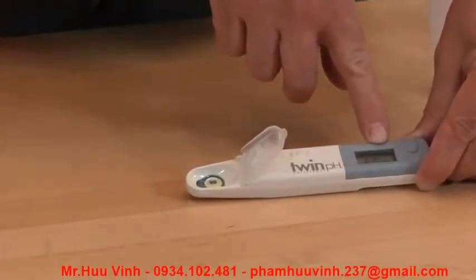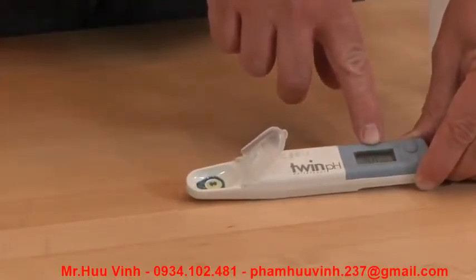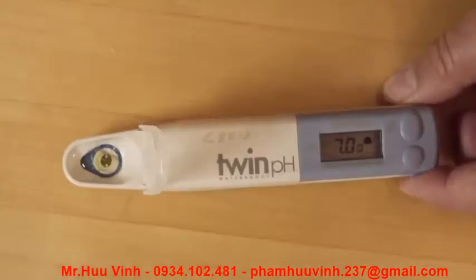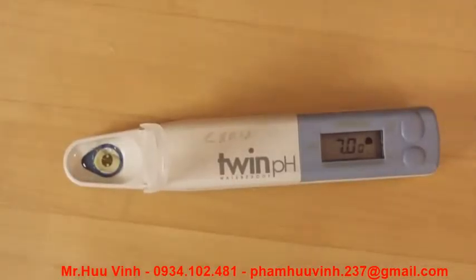you can see that we're at 6.99. We want to calibrate to this, so we push the calibrate button, and you can see we're calibrating to 7.00, and we have that little symbol showing we're in calibration mode. Now we just wait for the happy face, and we've done our calibration to pH 7.